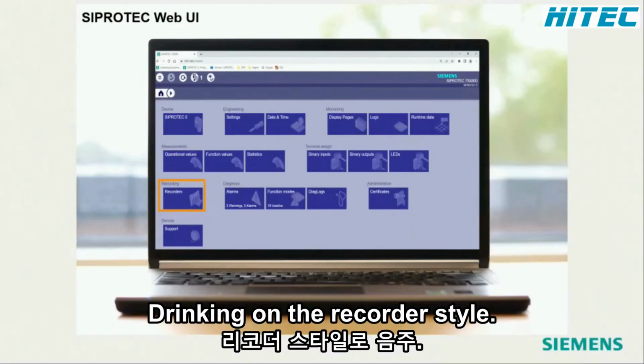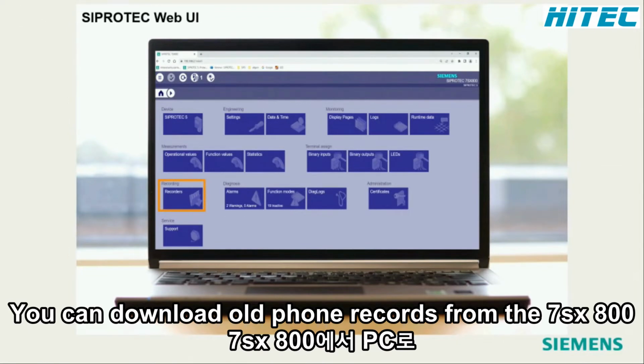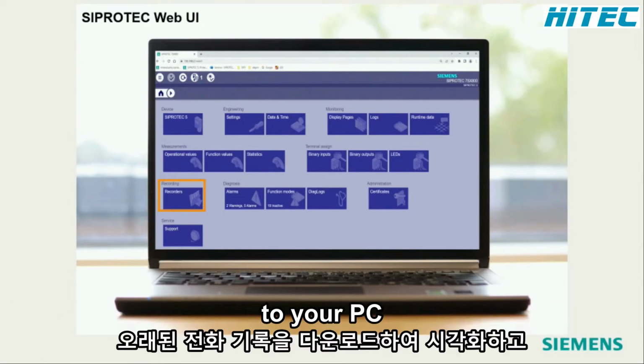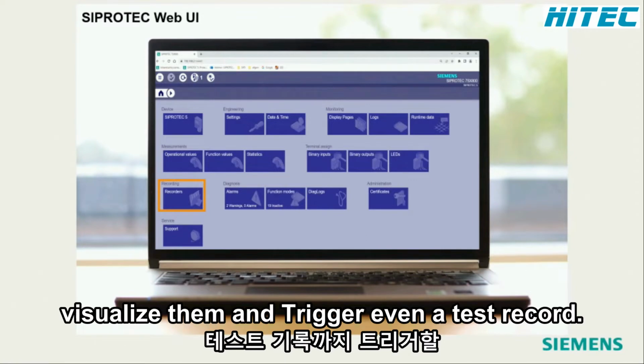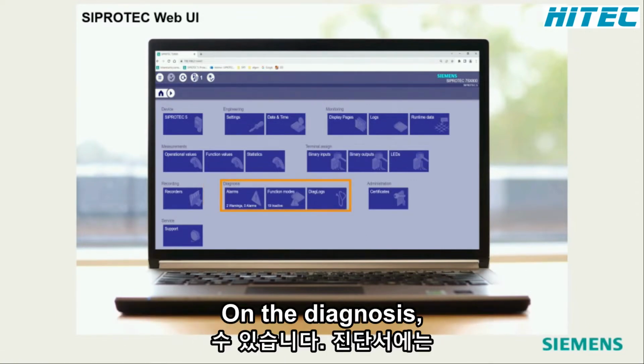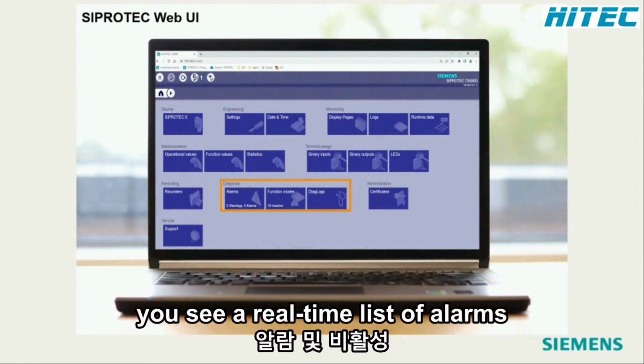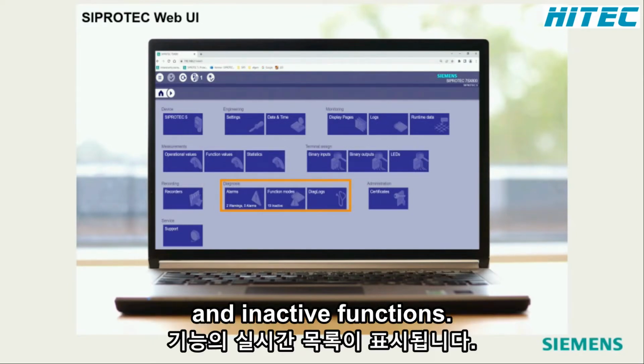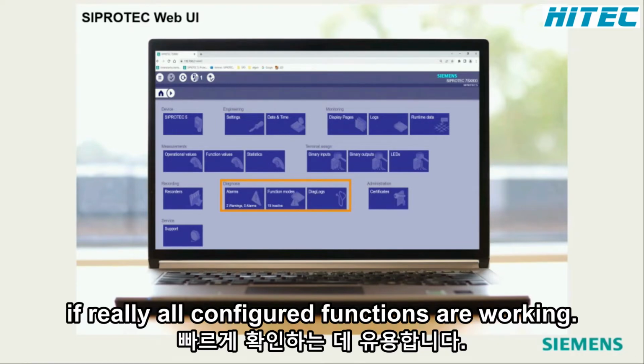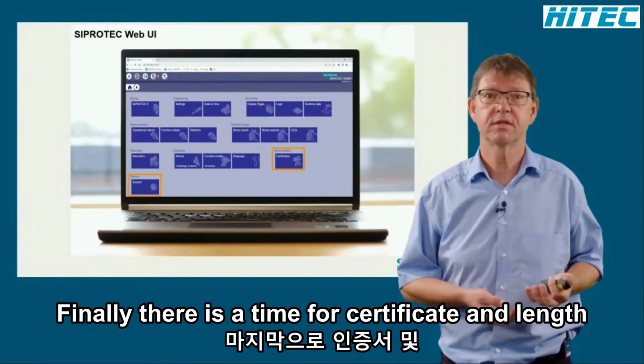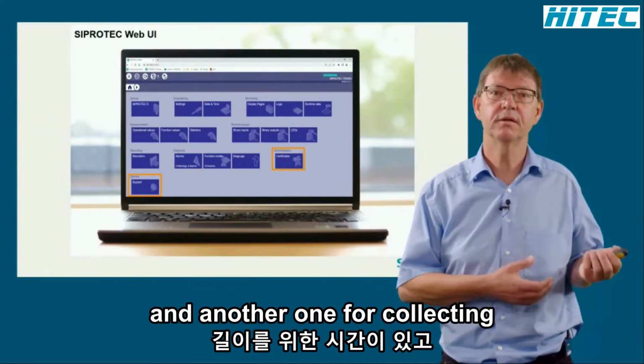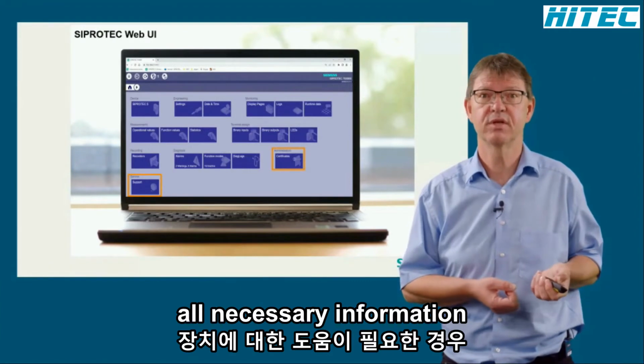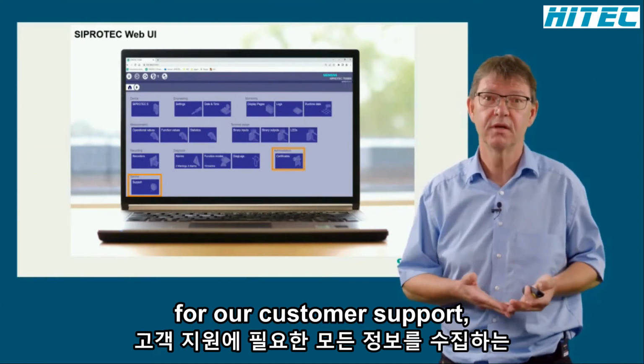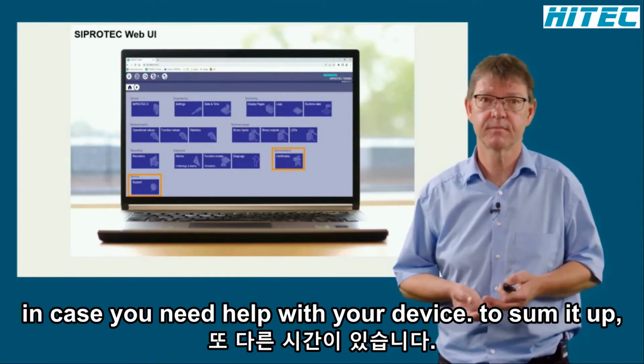Clicking on the Recorders tile, you can download all fault records from the 7SX800 to your PC, visualize them, and trigger even a test record. Under Diagnosis, you see a real-time list of alarms and inactive functions. This is good for a quick check if really all configured functions are working. Finally, there is a tile for certificate handling and another one for collecting all necessary information for our customer support in case you need help with your device.